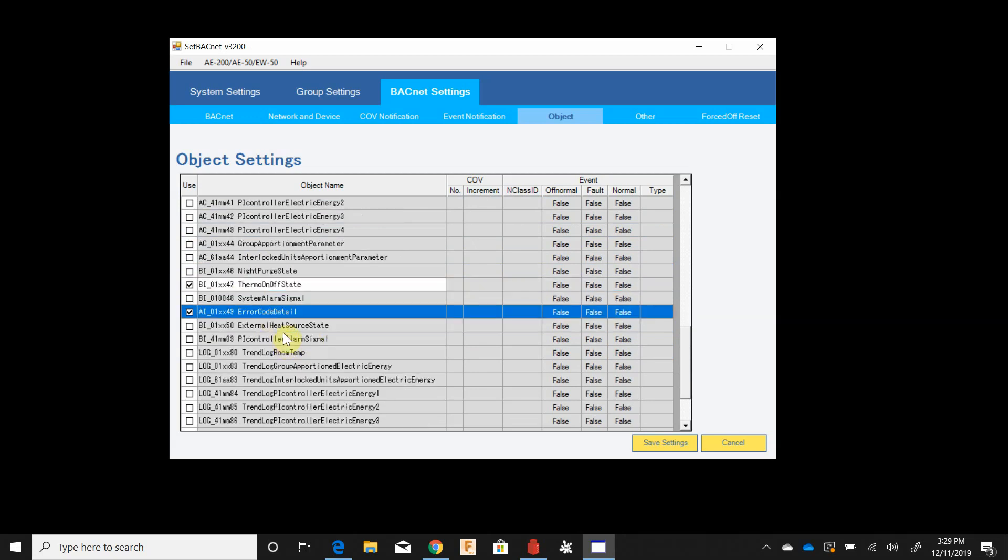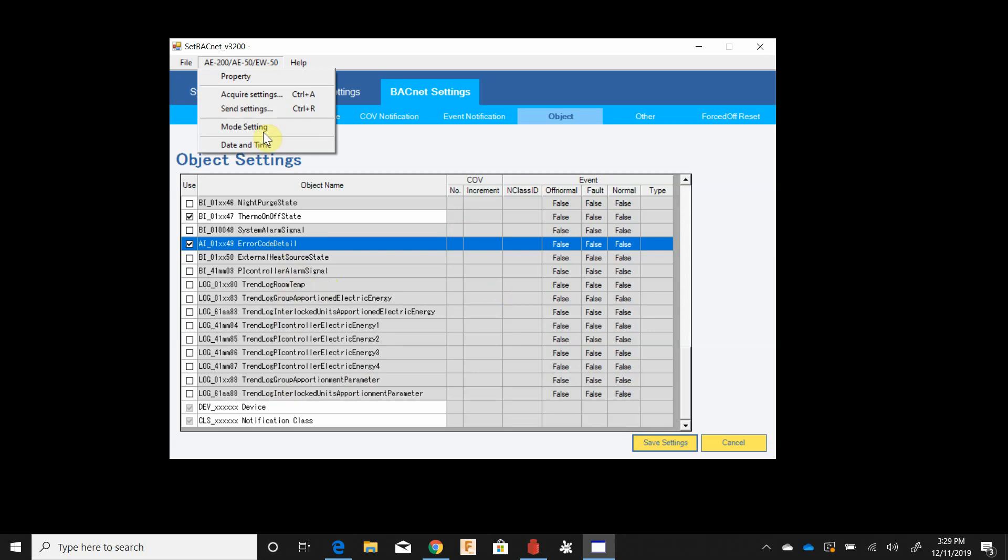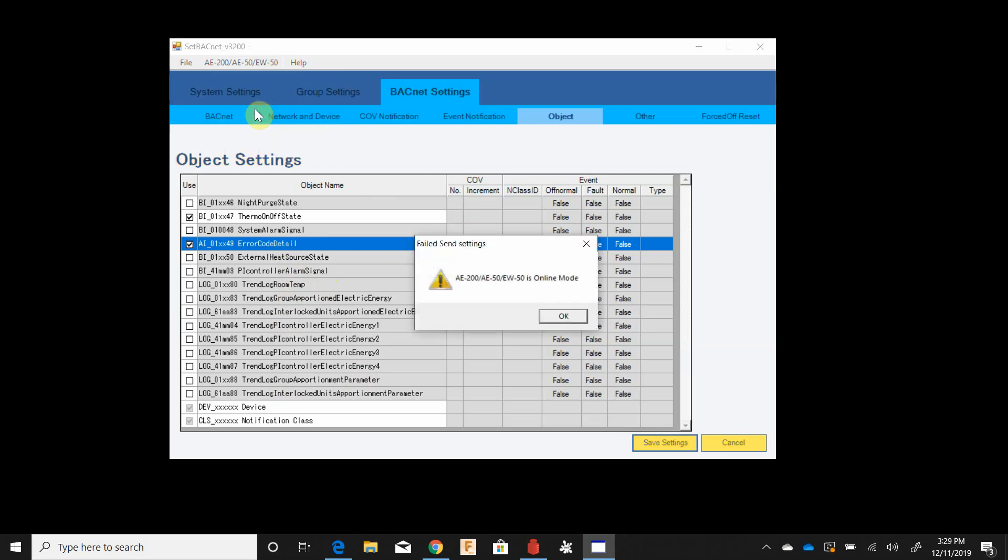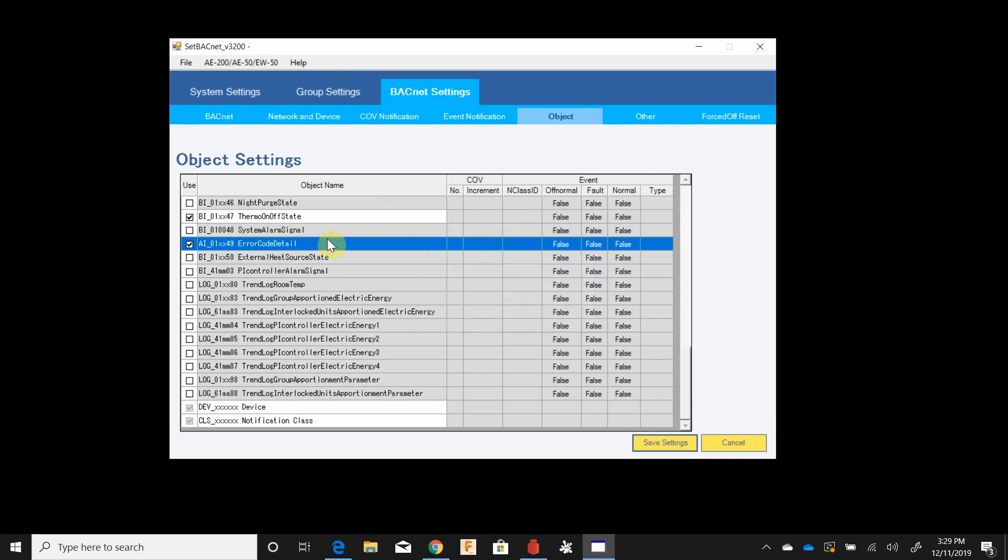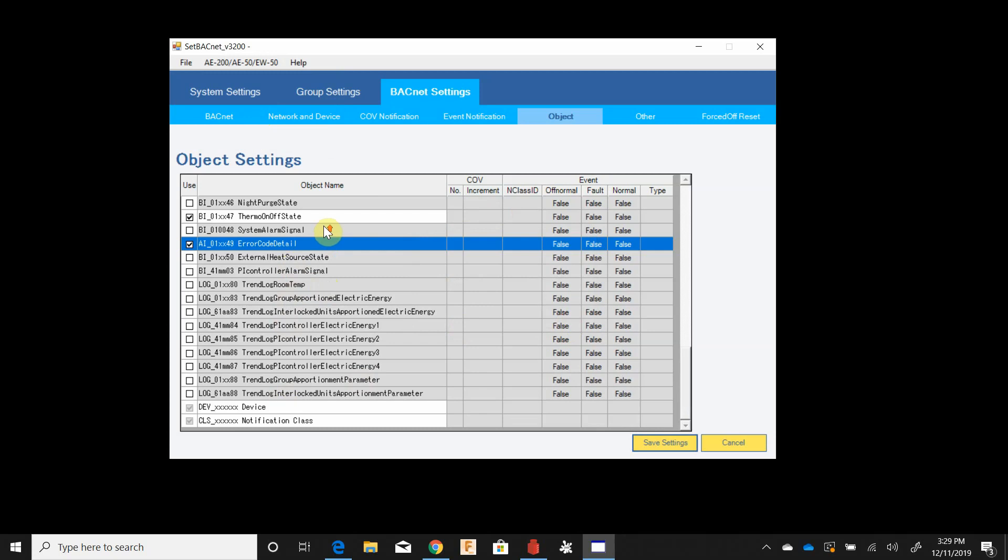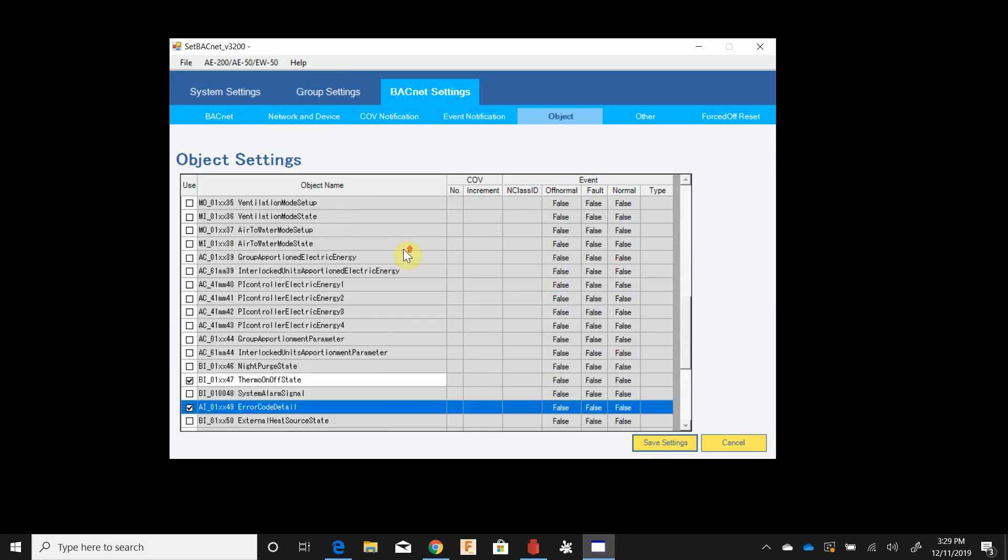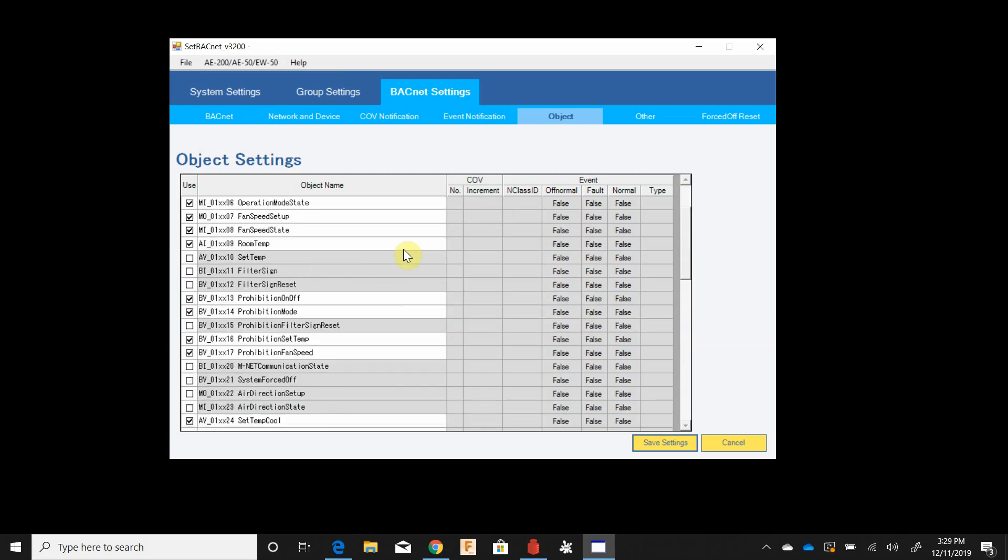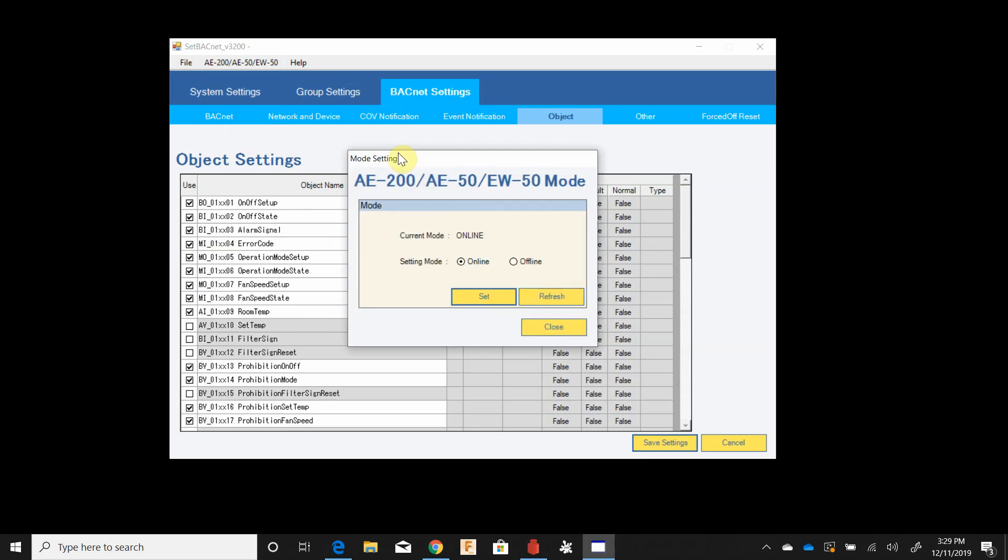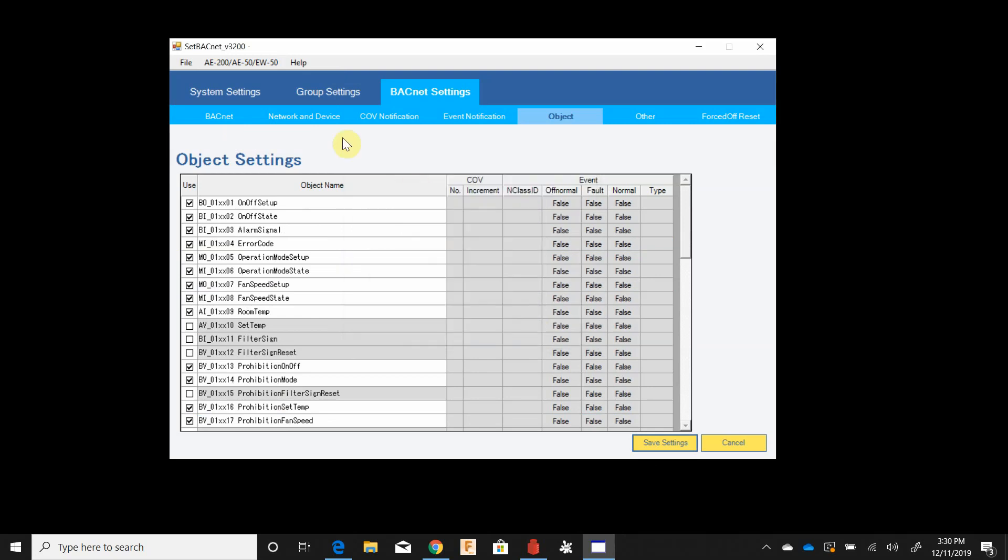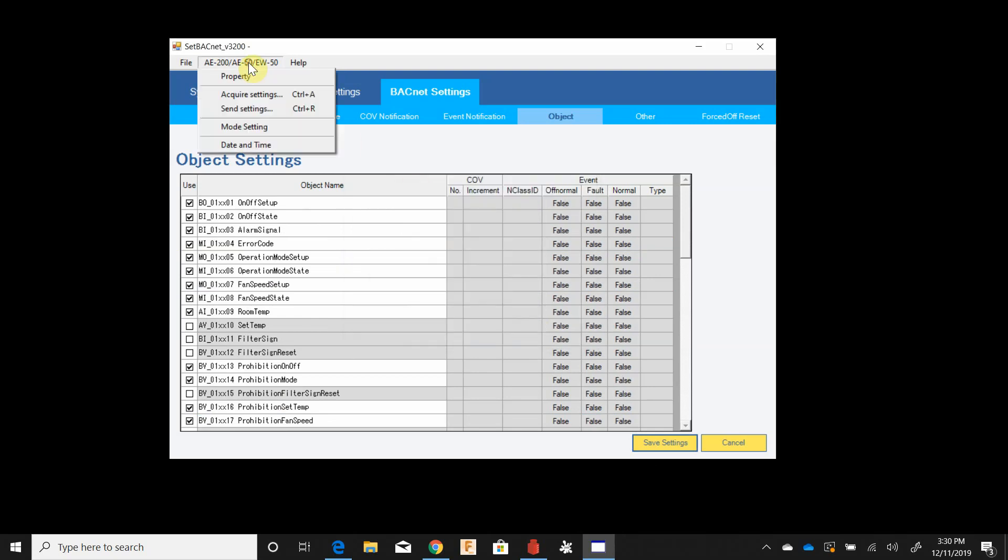Our error code detail there and then we've got some other stuff, some trend objects that have to do with the energy apportionment. So I'm going to save the settings now. I'm going to send my settings to the controller. It popped up an error that this is in online mode, this is because I previously set this panel up. You may not run into that the first time you set this up. If it's in online mode you need to set your mode settings, go ahead and click the button for offline and hit set. May I set offline mode? Yes. We hit refresh, it shows current mode is offline. This means I can send my settings now.